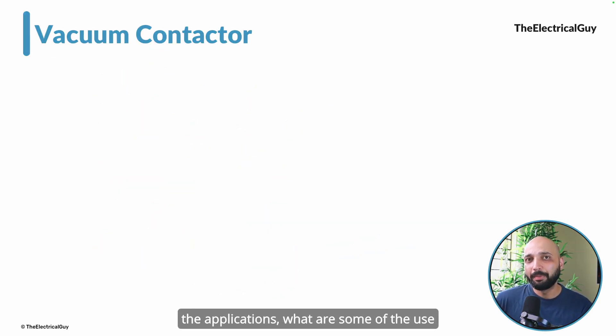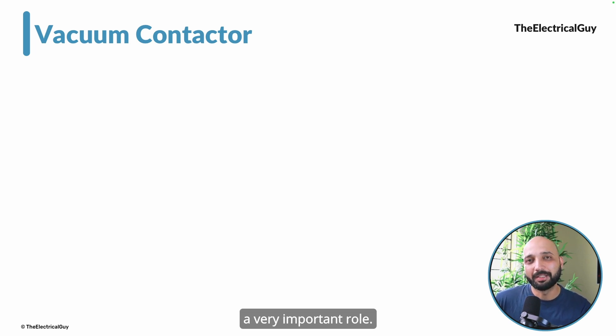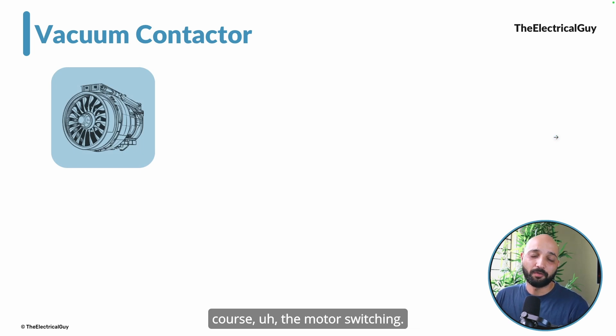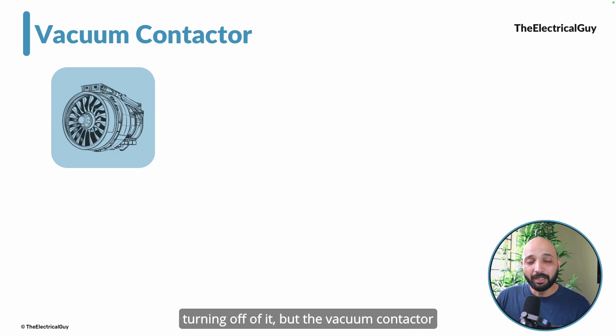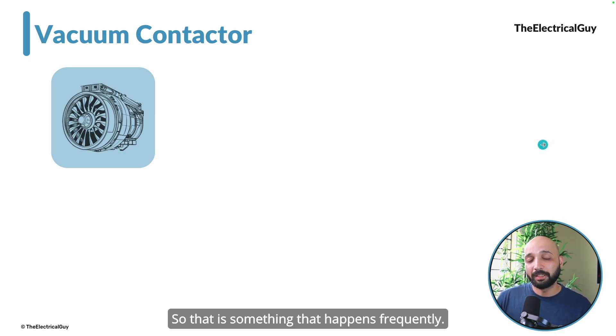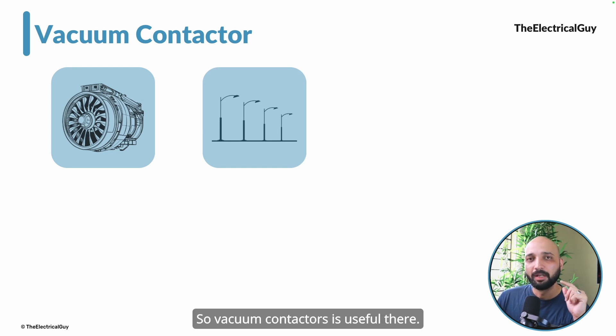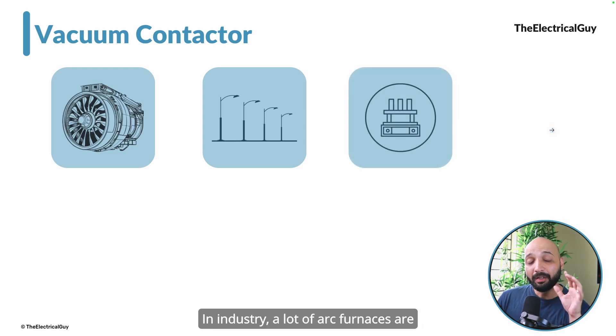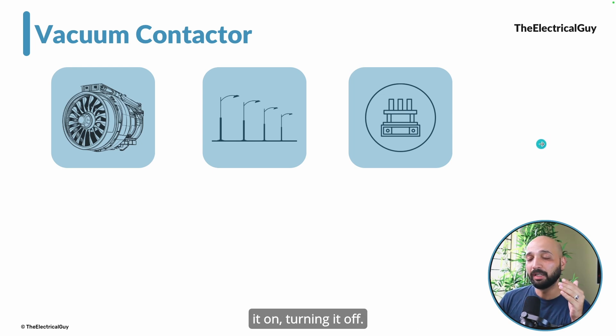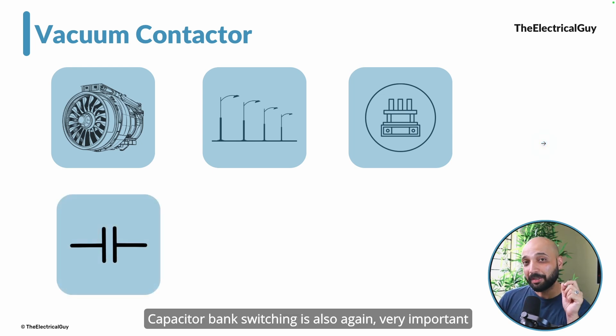Now let's talk about applications. The major application is motor switching — not just turning the motor on and off, but also reversing the direction of rotation, which happens frequently. Vacuum contactors are also used in power distribution, for example controlling street lights, which require many switching operations daily. In industry, arc furnaces need frequent switching, and vacuum contactors are well suited for that as well.